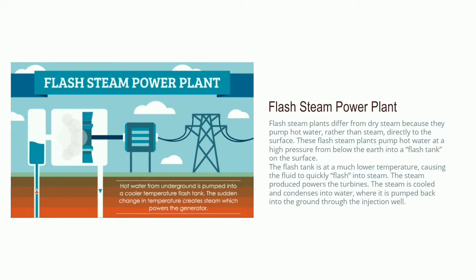The third type is the flash steam power plant. Flash steam uses a geothermal reservoir with water at a temperature greater than 360 degrees Fahrenheit. As it flows upward, the pressure decreases and some of the hot water boils to steam. The water and steam are separated, and the steam powers the turbine. Water is then recycled back into the reservoir. This is the most common type of geothermal power plant.